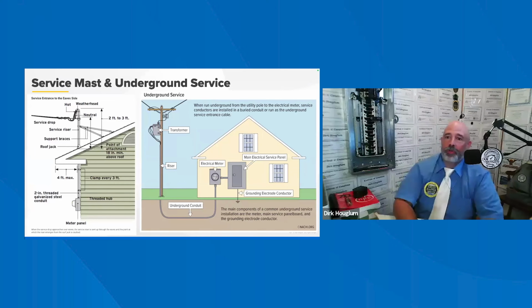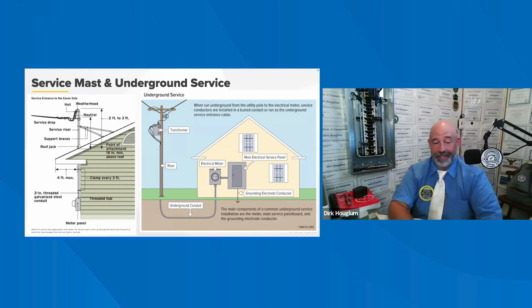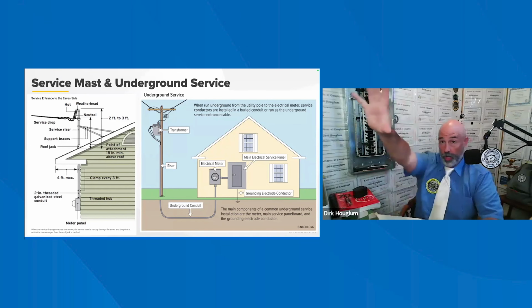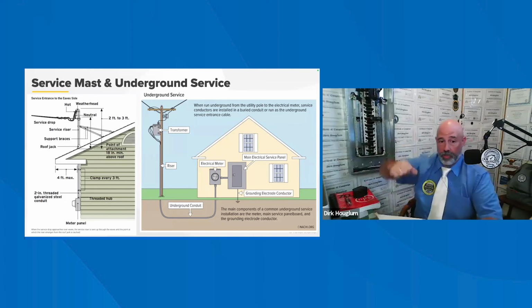When the service drop is located above the eaves, the service mast or the riser is run through the eaves. When the run is underground from the utility pole to the electric meter, service conductors are installed in buried conduit or run as an underground service entrance cable. So that's kind of how that works. So we have an electrical pole out here, and we actually have everything running in conduit right to the house.